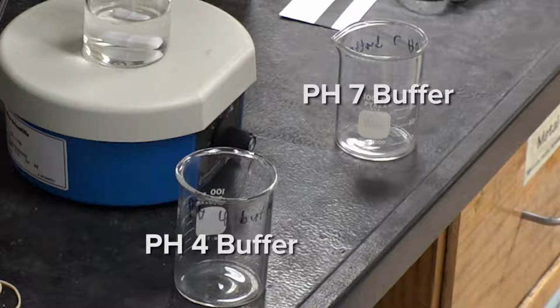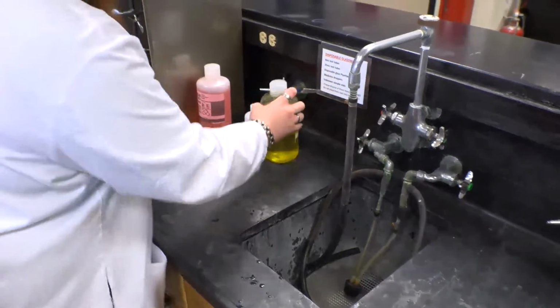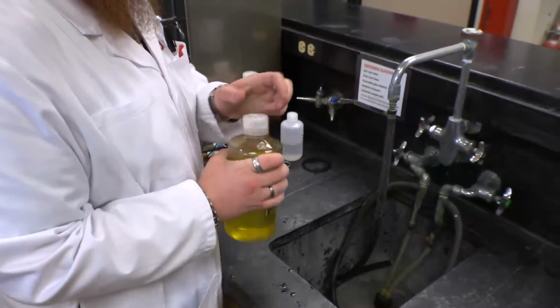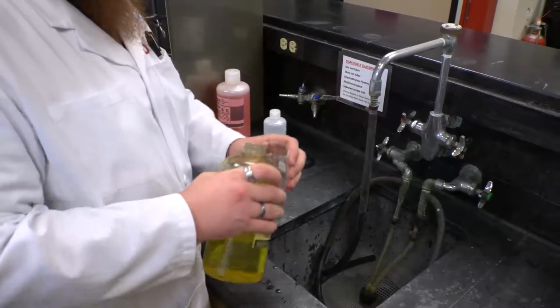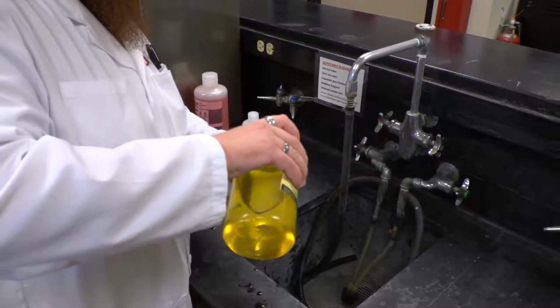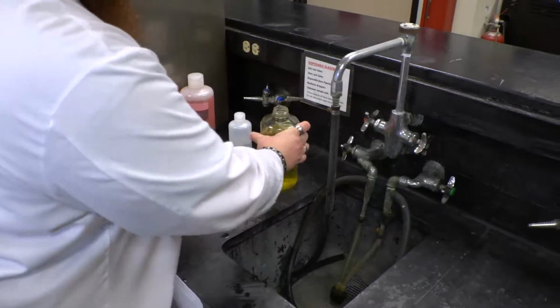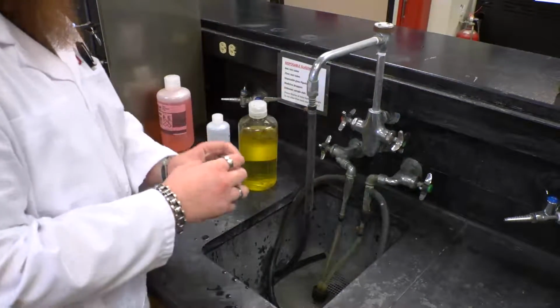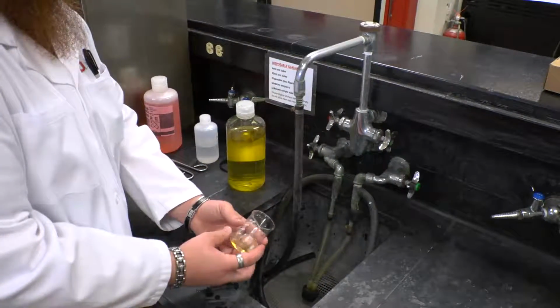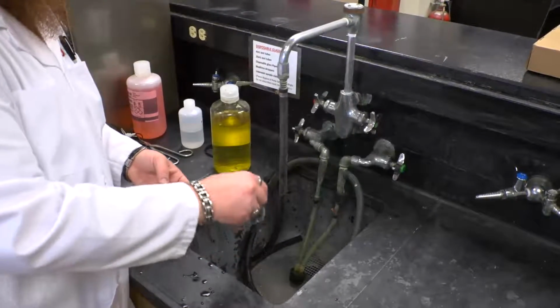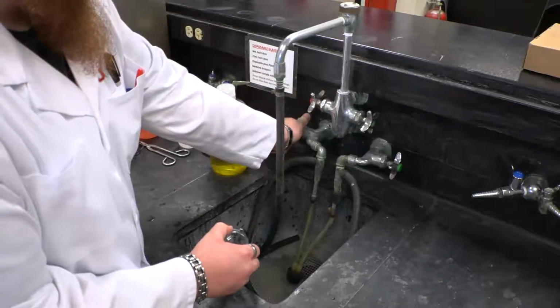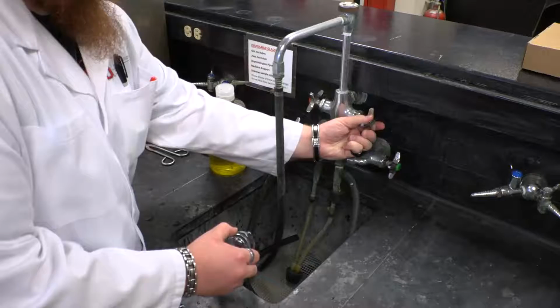For this, you need to obtain 2 clean, dry 100 ml beakers. You want to label your beakers, one with pH 4 buffer, the other with pH 7 buffer. The pH 4 buffer is normally a pink solution, while the pH 7 buffer is a yellow solution. You want to rinse out each of your beakers with about 10 ml of its corresponding buffer. The rinse can be washed out in the sink with cold running water. Once you have rinsed your beakers with their corresponding buffer solutions, fill each beaker with about 40 ml of its corresponding solution.